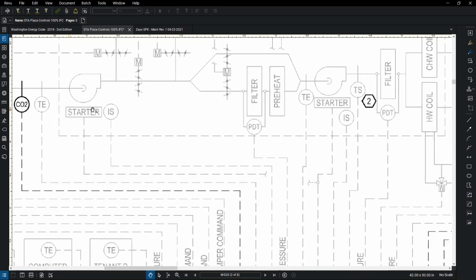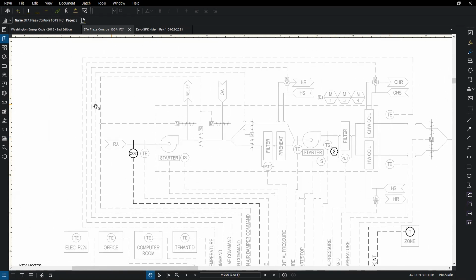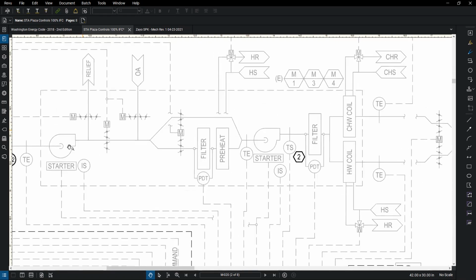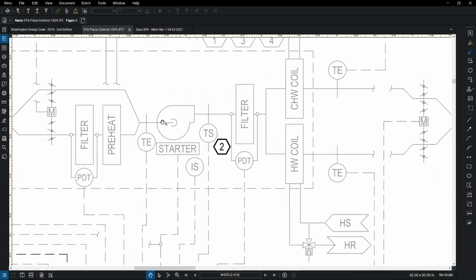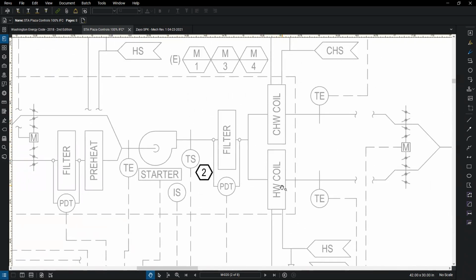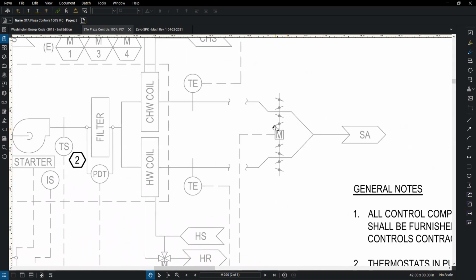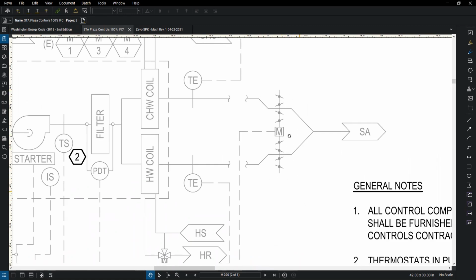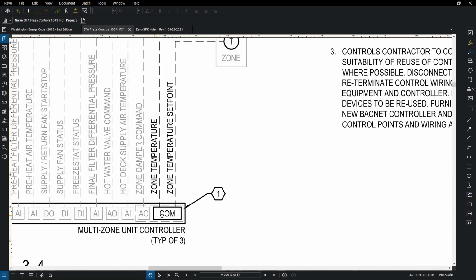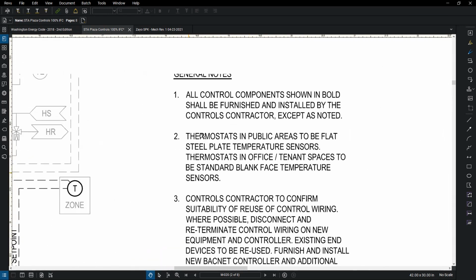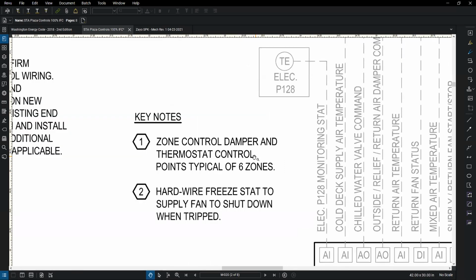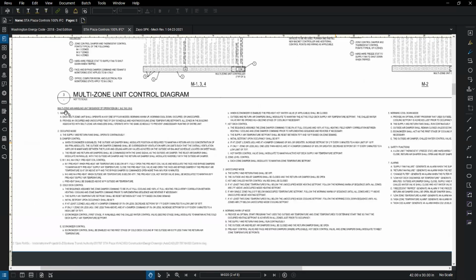Then you get to the multi-zone unit. So you can see there's a lot more going on here. But at the end of the day, we have our common supply fan, we have a chilled water coil and a hot water coil. And then we have our common actuator that's blending a bunch of cold and hot air streams. So we show one of these as kind of a representative. And if we follow that wire back, keynote 1, well, what does keynote 1 say? So there'd be 6 of those dampers on that one unit. And then more narrative description of what's going on. How's this thing supposed to run?